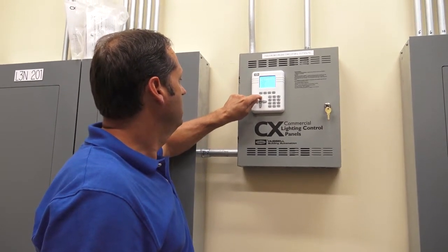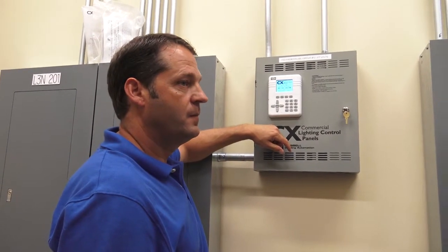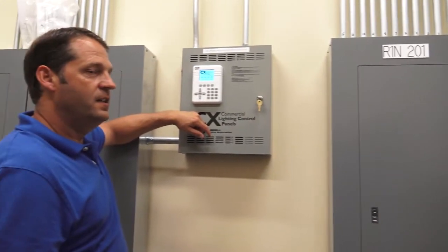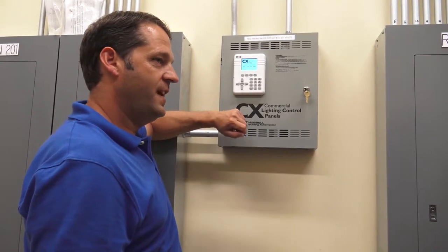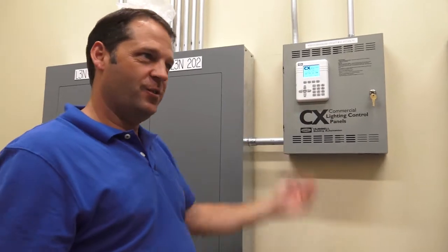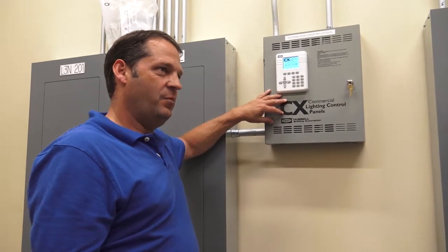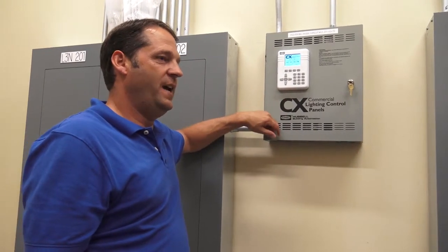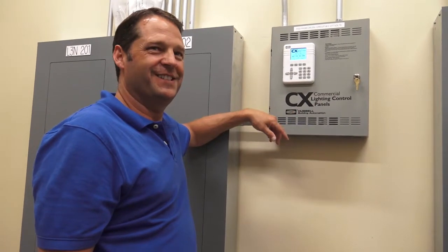That is pretty much it. What's the most common problem you have with them? Honestly, the only problem I ever had, and it was another standard job, after power loss, they lost their program. I went back and reprogrammed it a couple of times, and I'm like, there's obviously something going on. It was a newer panel. Well, there's the battery. So we put a new battery in it and we fixed it.